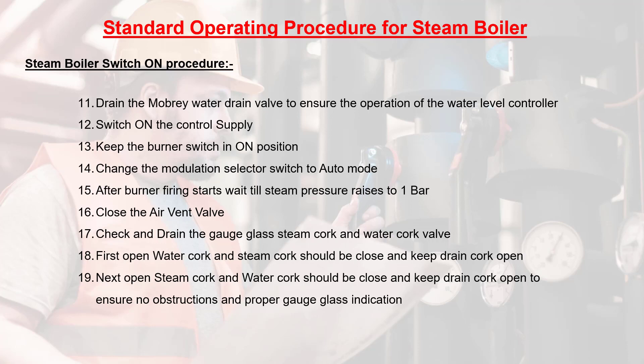Step 13: keep the burner switch in the ON position. Step 14: change the modulation selector switch to auto mode. Step 15: after burner firing starts, wait until steam pressure reaches 1 bar.